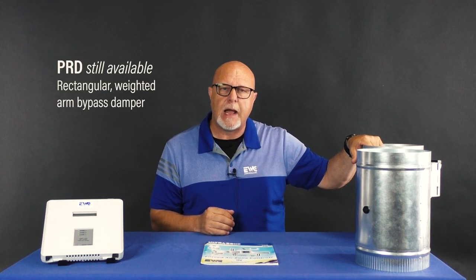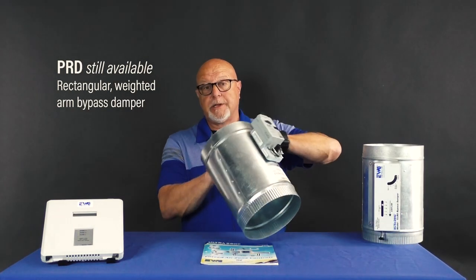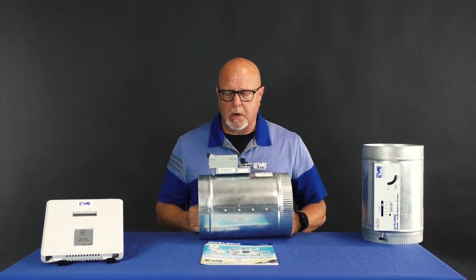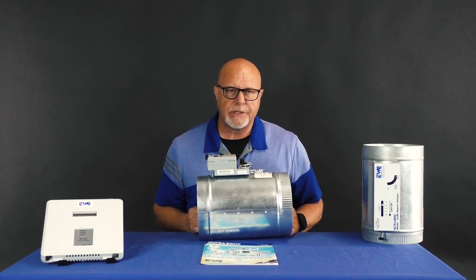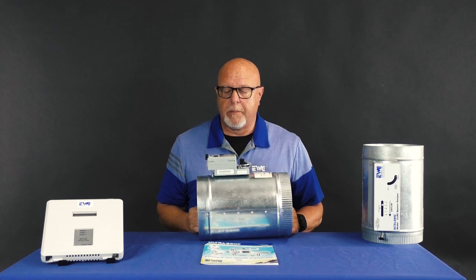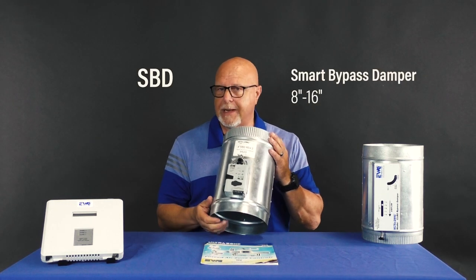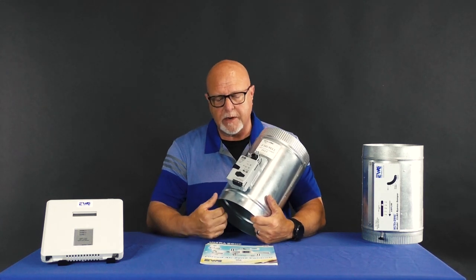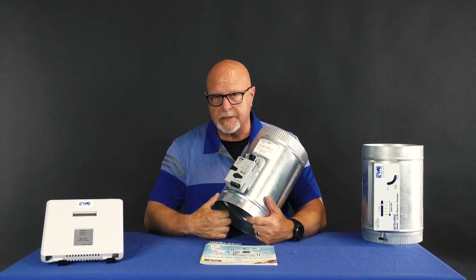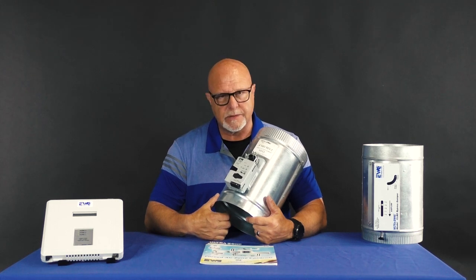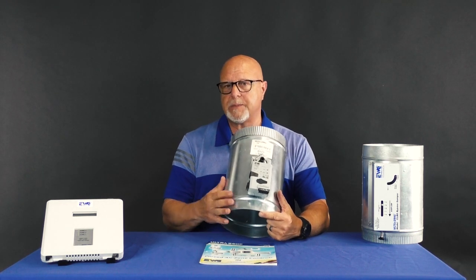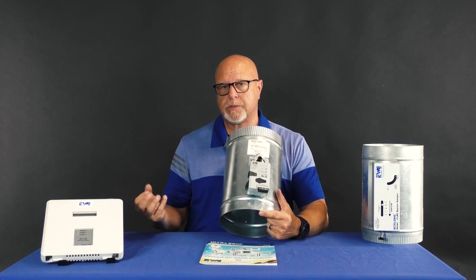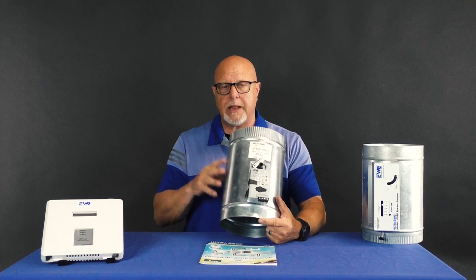We still have available the old PRD, which is our weighted arm. It's still a weighted arm, but it is one of the only rectangular weighted arm bypasses out there in the industry, and that's still available. Moving forward to a more accurate and easy to install bypass is our Smart Bypass, or SBD. Contractors are quickly becoming very familiar with this, as it is the easiest to set up, and it is very, very accurate. Coming with the SBD, you will get tubing and you will get pitot tubes, which will be installed in the supply and the return.